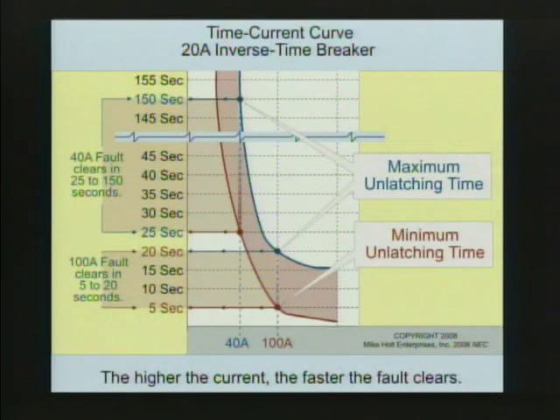All right, let's take a look at the next slide here. And Eric, you mentioned something about a 15 amp breaker carrying 75 amperes. Well, this is a time current curve. Let's go with a 20 amp breaker. And if you took it 5 times, well, 15 times 5 is 75, but let's just go 20 amperes times 5. So at 5 times, this first line right here is the minimum unlatching time, and that's the maximum unlatching time. At 5 times, the minimum is 5 seconds, and the maximum unlatching time is going to be 20 seconds.